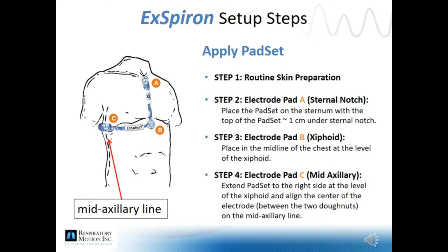After the pad set has been placed on the patient, connect the tail of the pad set with the black connector to the white patient cable coming from the ExSpiron. You can affix the clip, which is located on the white patient cable, to the patient gown to assist in preventing any added tension of the cable and/or the pad set.